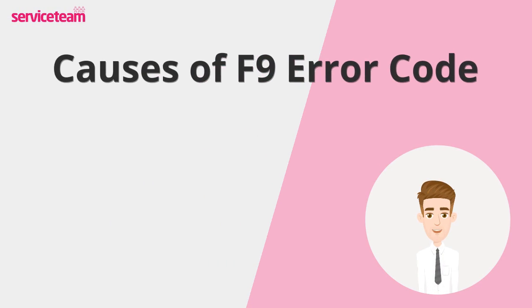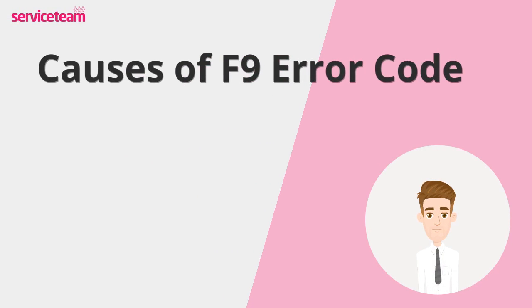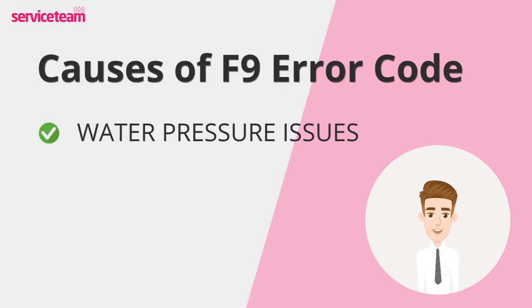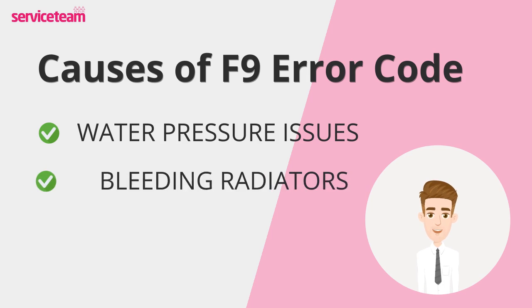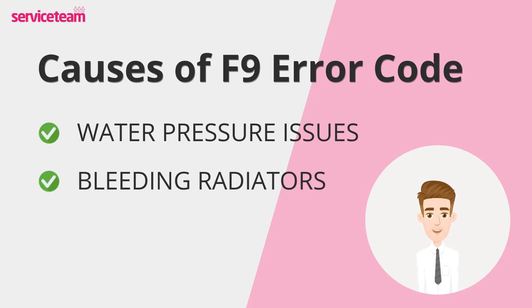Let's see what causes the F9 error. The F9 fault can be triggered by low or high water pressure. If your system's pressure falls outside the recommended range, your boiler can't operate safely. This can happen due to leaks in the system, which cause a drop in pressure, or blockages and airlocks that affect the water pressure. Bleeding your radiators can sometimes lead to pressure loss if too much water escapes.